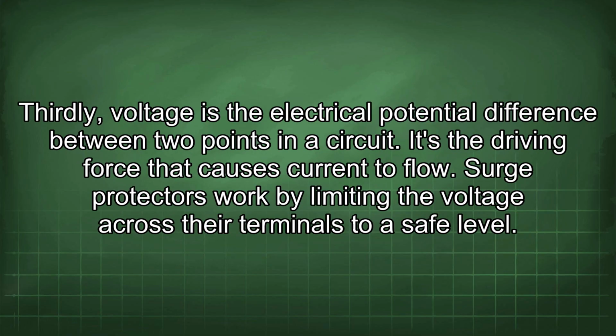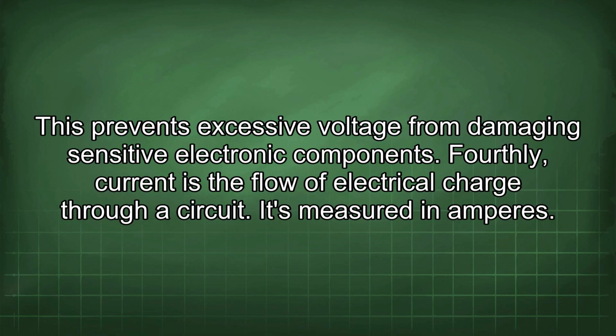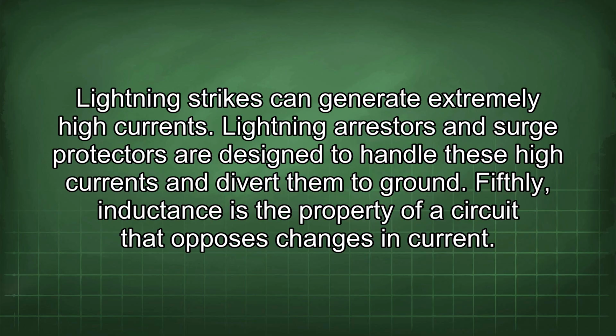Thirdly, voltage is the electrical potential difference between 2 points in a circuit. It's the driving force that causes current to flow. Surge protectors work by limiting the voltage across their terminals to a safe level. This prevents excessive voltage from damaging sensitive electronic components. Fourthly, current is the flow of electrical charge through a circuit. It's measured in amperes. Lightning strikes can generate extremely high currents. Lightning arresters and surge protectors are designed to handle these high currents and divert them to ground.